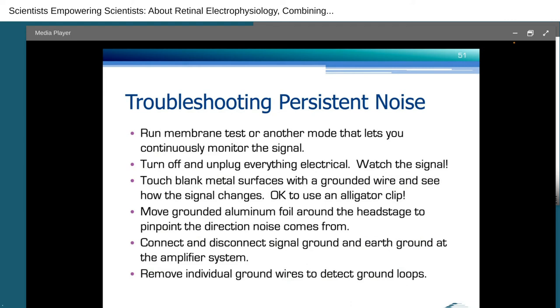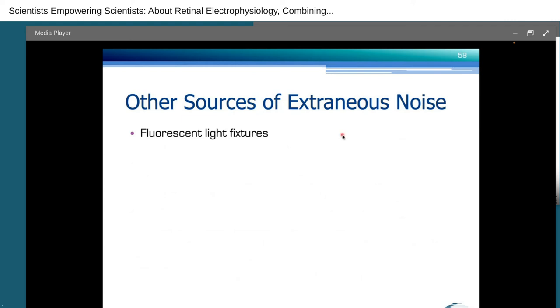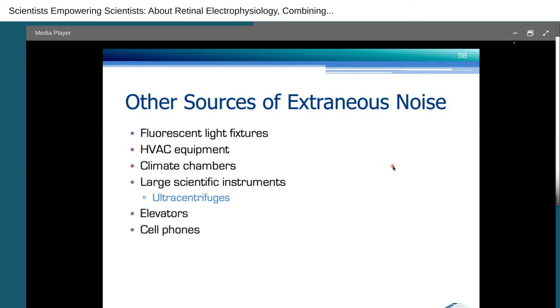You want to turn off and unplug everything electrical and watch your signal change. If it changes when you unplug something, then there you have your culprit. You want to touch blank metal surfaces with a grounded wire and again see how the signal changes. When I touch this screw near my objective mount on the microscope, and all of a sudden my line frequency hum goes away, then there you have your culprit. For this, it's okay to use an alligator clip. Only if you have identified a component, then use a banana or some other more reliable connector. You want to move a grounded sheet of aluminum foil around the head stage to get an idea of what direction the noise may come from. You may have to connect or disconnect the signal ground and earth ground at the back. Also what helps is removing individual ground wires to detect ground loops. In general, you want to not leave ground wires in place that don't give you a benefit. If it doesn't make it better, then there's a pretty good chance that it makes it worse. And with that, what I'll do is I will skip ahead a little bit, skip the second use case scenario with P over N leak subtraction and go to other sources of extraneous noise.